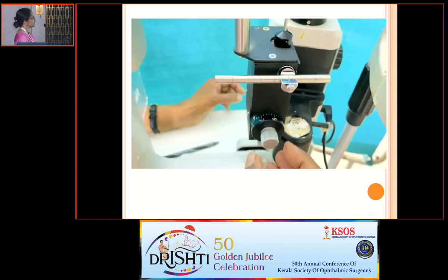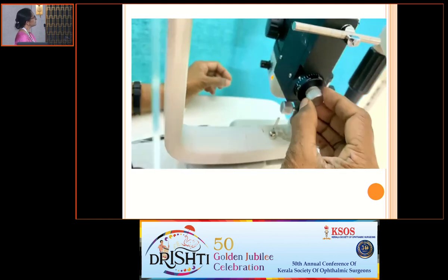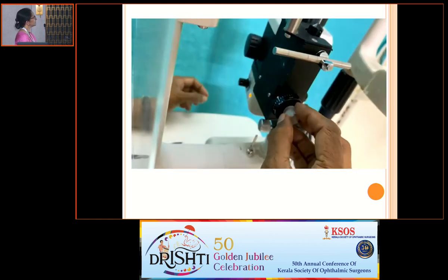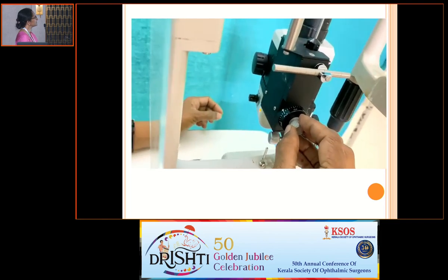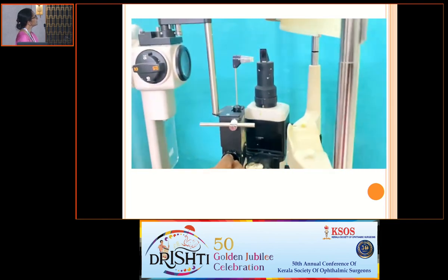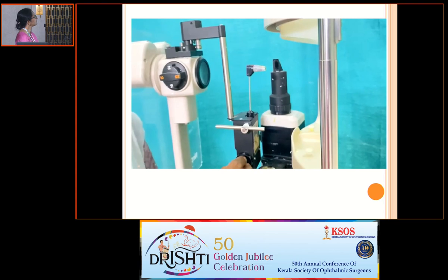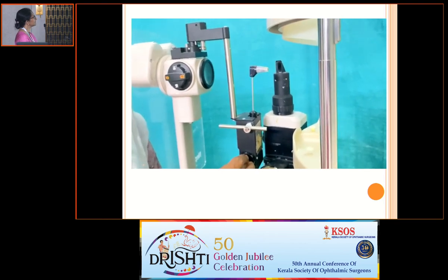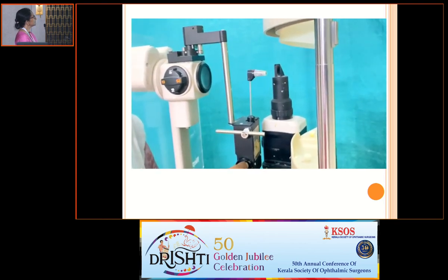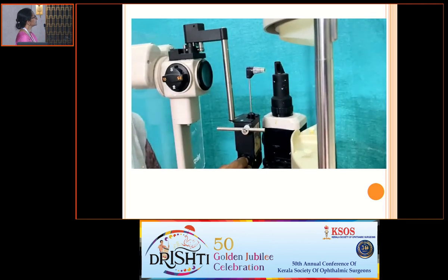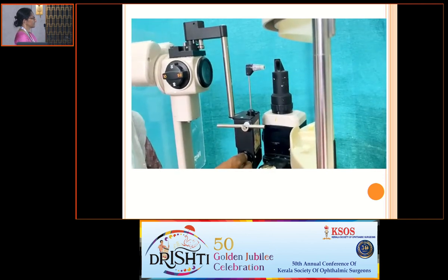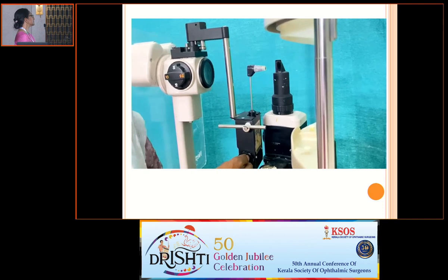adjustable holder. Turn the knob to position 2 and now rotate the knob a little forwards, about 0.5 millimeters of mercury, and we can see a forward movement of the feeler arm and the tonometer head. And now rotate the knob a little backwards and we can see a backward movement of the feeler arm with the tonometer head.